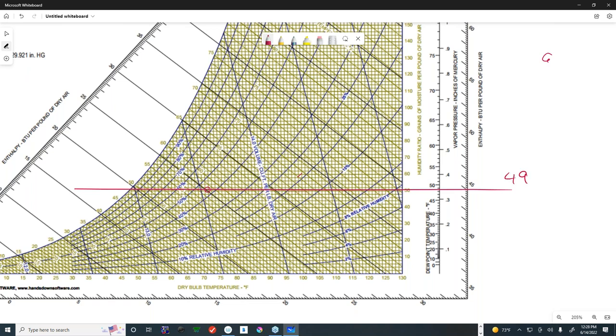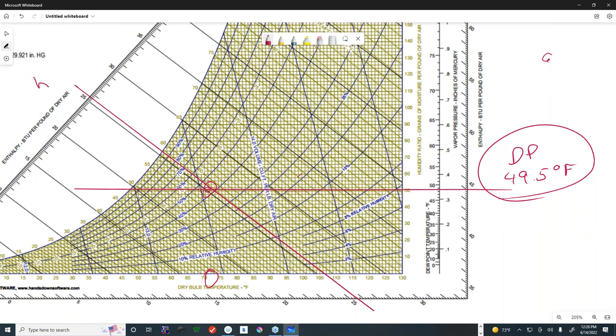So you can see that's pretty close to 49.5 degrees Fahrenheit. So again, it was roughly 72 degrees down here, 45% relative humidity. And if we draw a line horizontally on the psychrometric chart, we can find the dew point temperature. So that's dew point. Dew point temperature is about 49.5 degrees. And since we're at that point, we can also find the enthalpy. So if I draw a line that is diagonal over here, we can see that it looks like 25.5. So there's my enthalpy, sometimes abbreviated as H. My H is equal to 25.5. That's BTUs per pound of dry air.